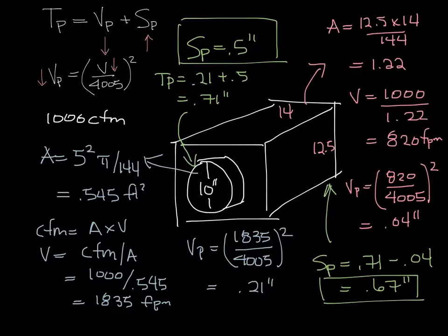Now there is some pressure loss across the box, but you can see that the static pressure is actually increased by lowering the velocity in the box. When the airflow expands and slows down in the rectangular section of a VAV box, you regain static pressure. Static regain is also a method of duct design, which I won't go into, but it is a good way to design ductwork for VAV diffuser systems, so we may do that in a future podcast. So that answers the question, what is static regain?